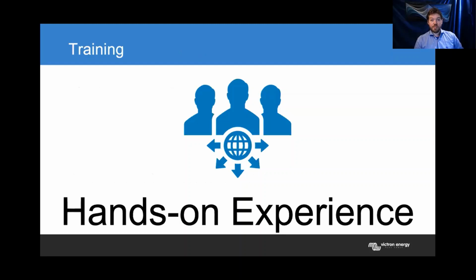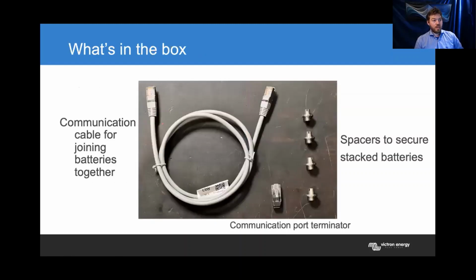After these slides, I'll run you through and we'll go outside to look at the system in action. Firstly, what you get in the box: a communications cable for joining the batteries together, the communications port terminator, and the spacing nubs to secure the stacked batteries so they screw in and the batteries can't slide off each other.